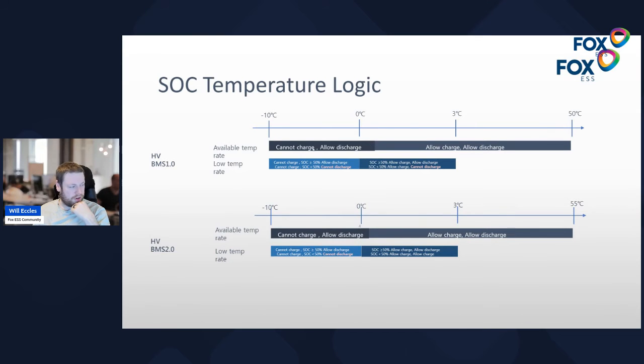You can see that as we go under 0 degrees, you can't charge, and you can discharge for a little bit, but it all depends on where your state of charge is. So if you're under 0, you can't charge, and you can't discharge if you're below 50%, but if you're above 50%, you can have a small amount of discharge energy from the battery below 0. So it effectively stops you from charging below 0, and it's heavily rate limited below 3 degrees. That's basically what most people see and experience: the batteries going offline when they get very, very cold. Again, this is just to protect them, completely normal.